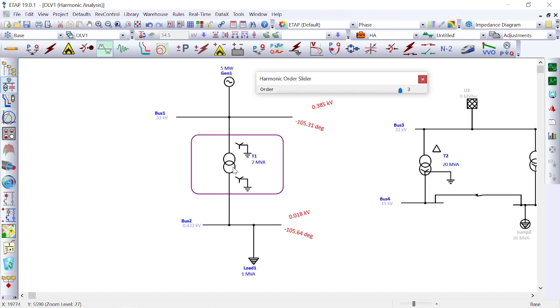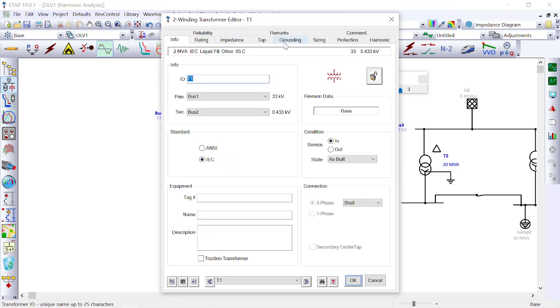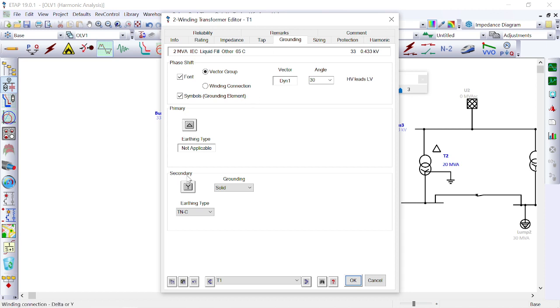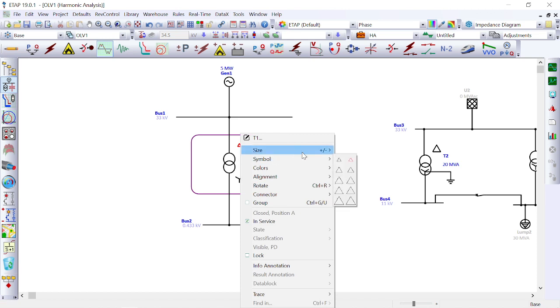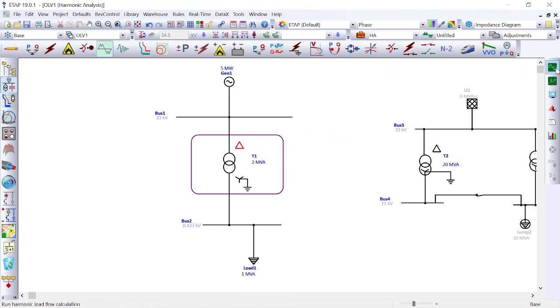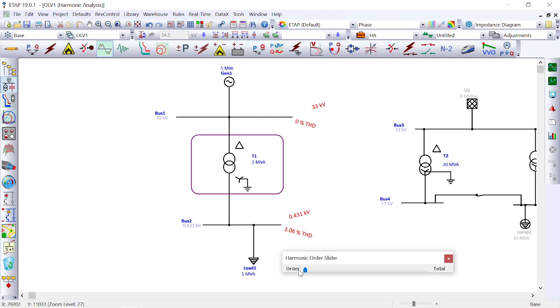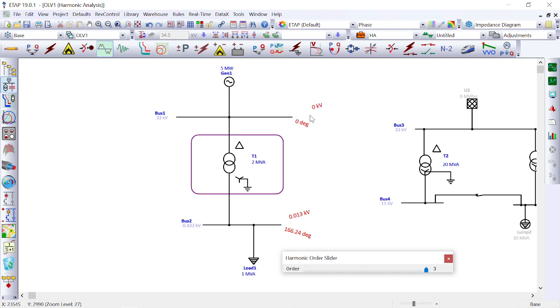Now let us change the winding configuration — instead of star, we select delta on the primary generation side. Running the harmonic load flow again, we can see total harmonic distortion is 3.06% THD overall, but on the generator side it is 0% THD — there is no harmonic present when delta is used. Going to the third harmonic, third harmonic voltage is zero — confirming that with delta on the inverter or generator side, third harmonic current is not transmitted.